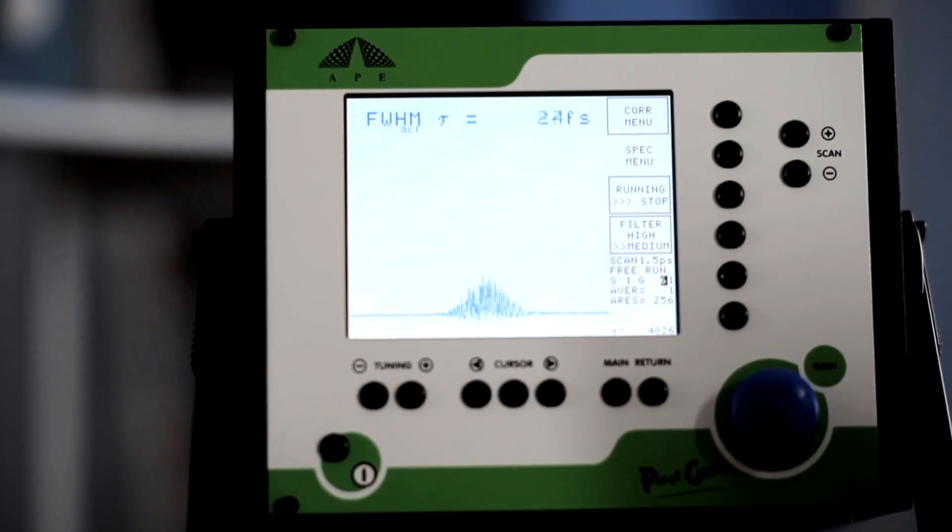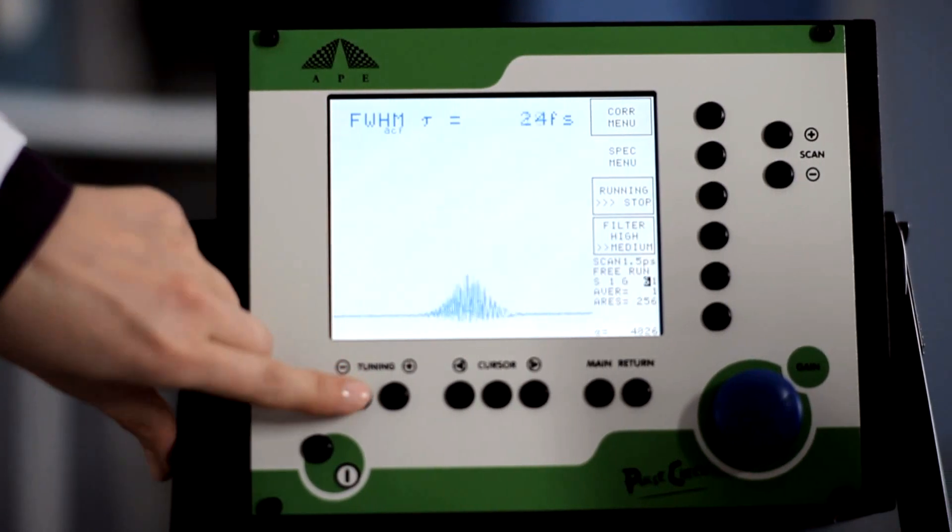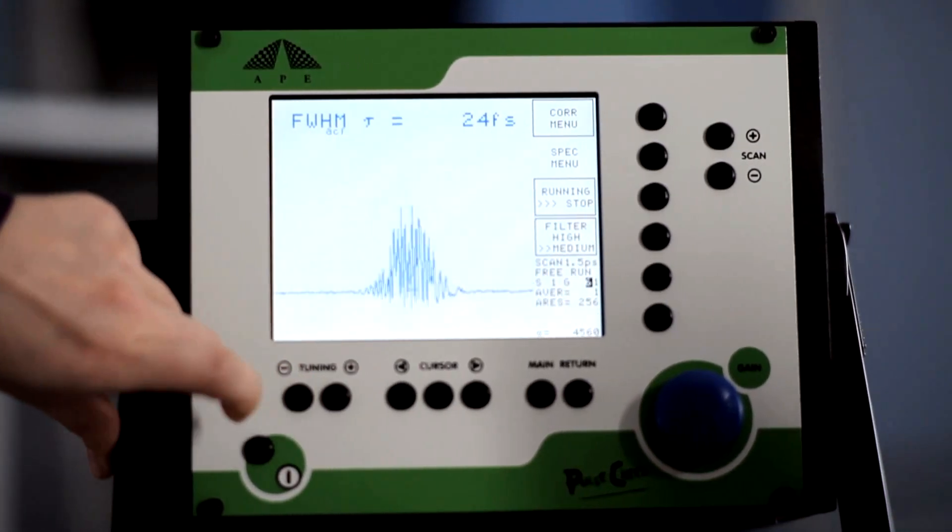Now you can direct the beam to the input aperture, by turning the input mirror screws in the appropriate direction. Once the beam is in the center of the crosshair, check the controller screen to see if you have a signal. If there is no signal, or if it's weak, press the tuning buttons to adjust the crystal angle.